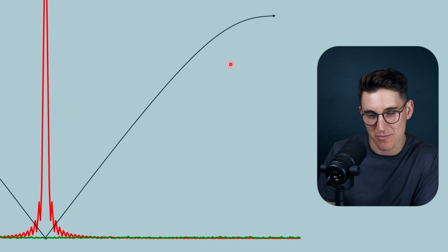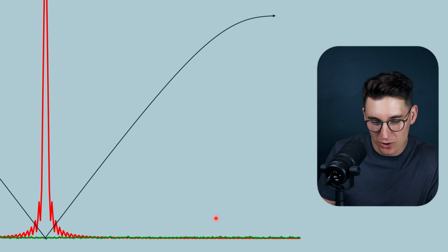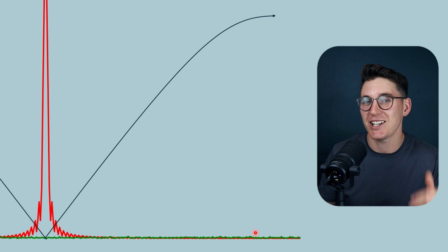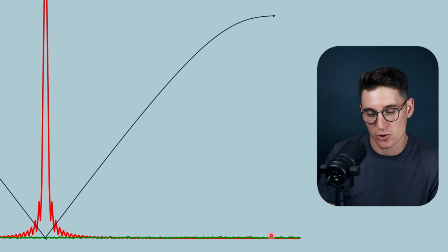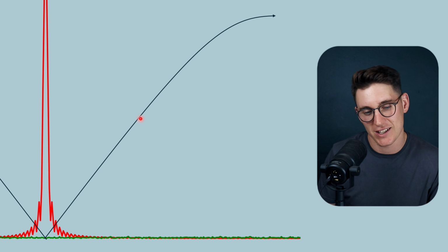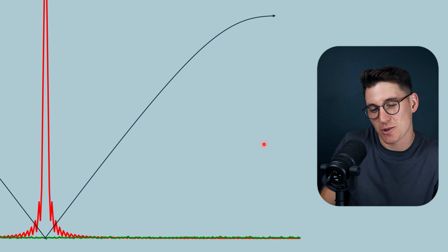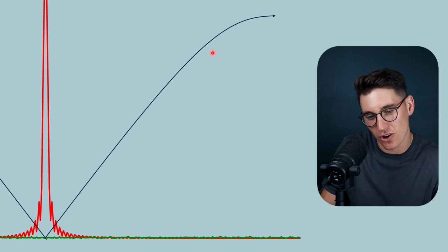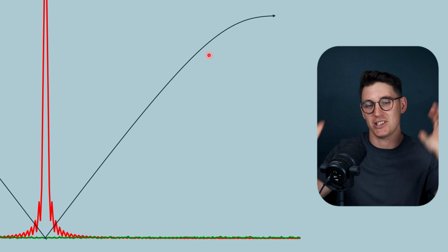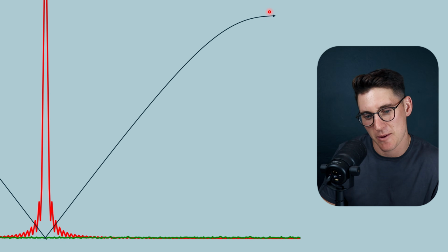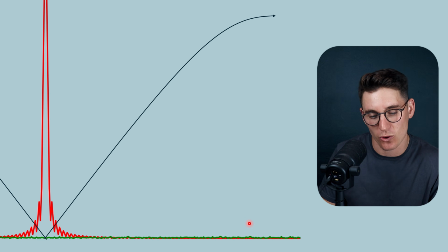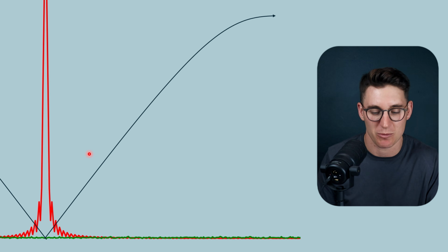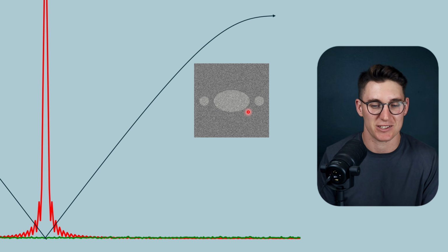If we apply the ramp filter, we will increase these higher frequencies. We're going to increase noise and we're going to increase the true higher frequencies from our image. This is the reason that the ramp filter curves up like this, in an attempt to suppress some of that noise that's being added into the image. However, even with the curving of this ramp filter, not just perfectly straight lines like you might see in some textbooks, we're still going to amplify noise here in the one-dimensional frequency domain and create an image that looks like this.